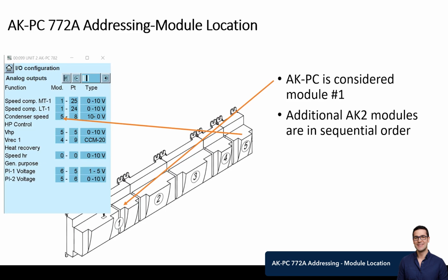This would be where we get in, and whether it's for an analog output, this is a screenshot of a fully controlled system. So more than what we would just see for high pressure and receiver bypass valves. So it wouldn't be as much to program in that replacement situation, but this is what the screen looks like, where you're essentially programming in two numbers. What module is it on?